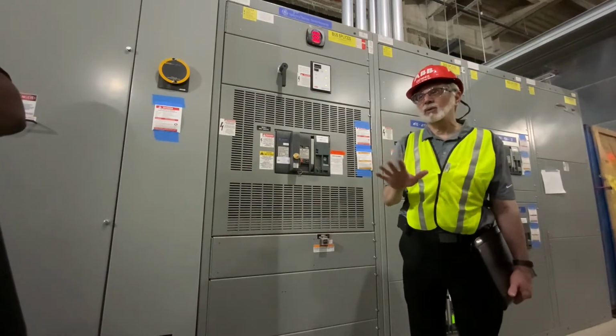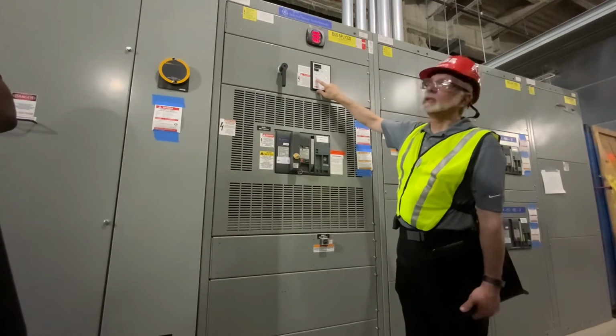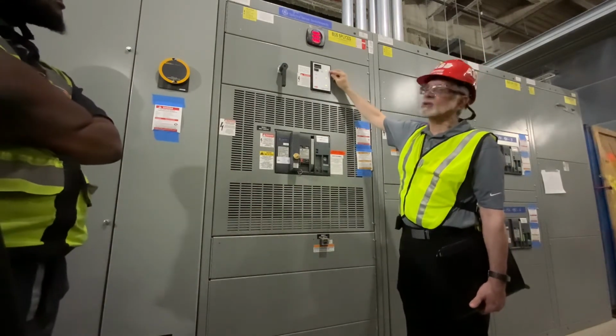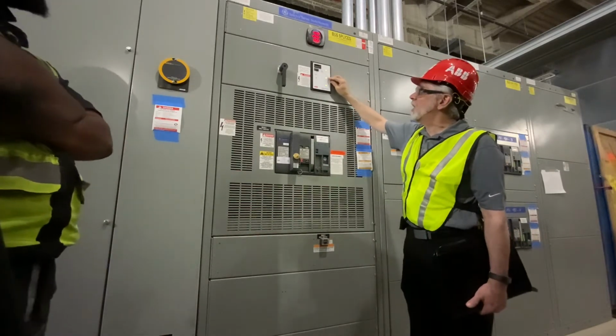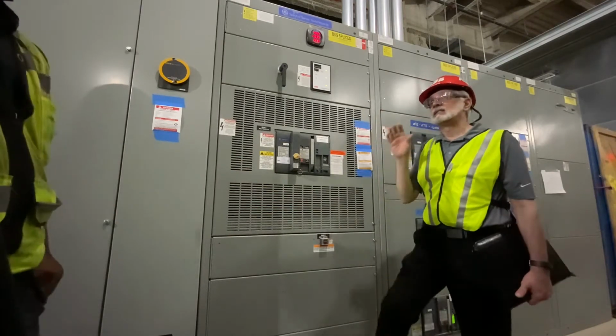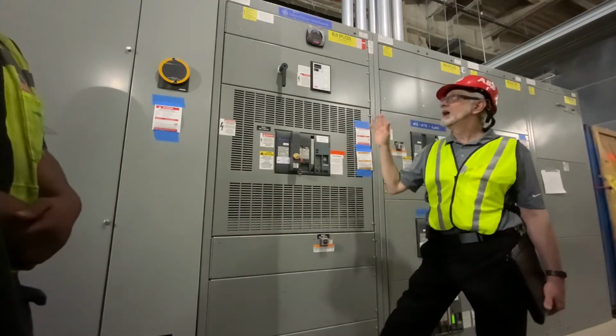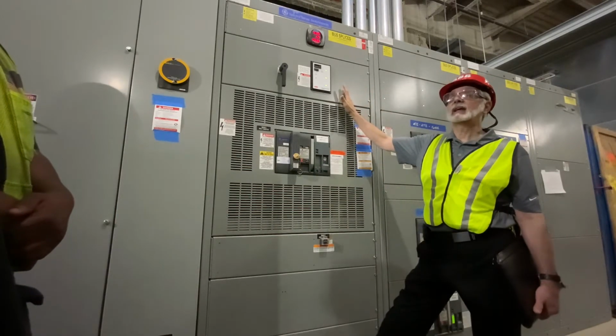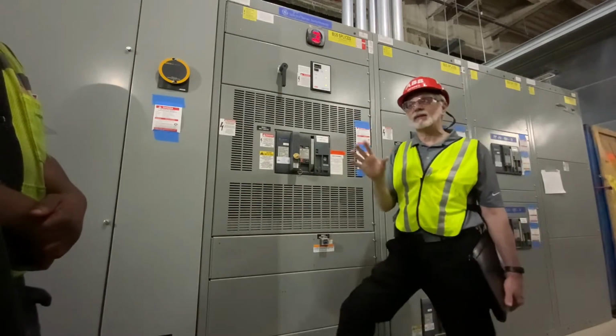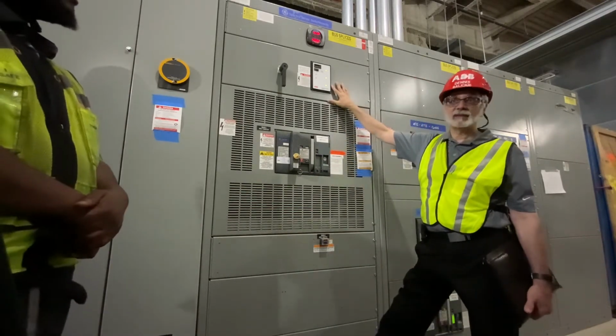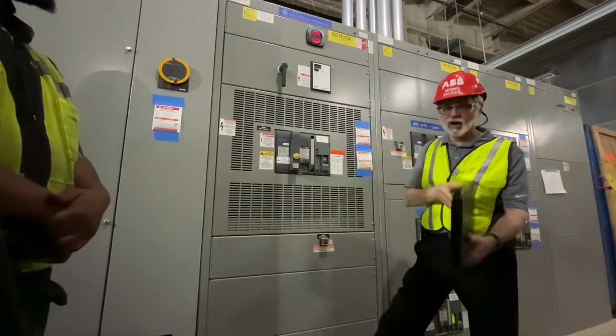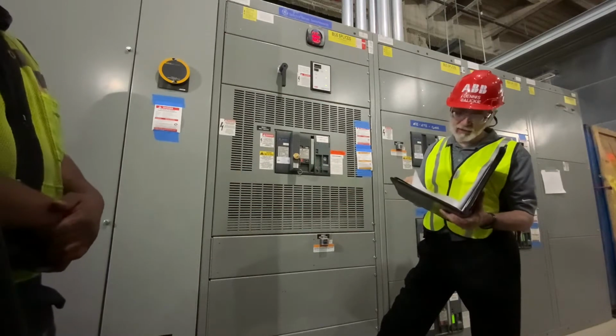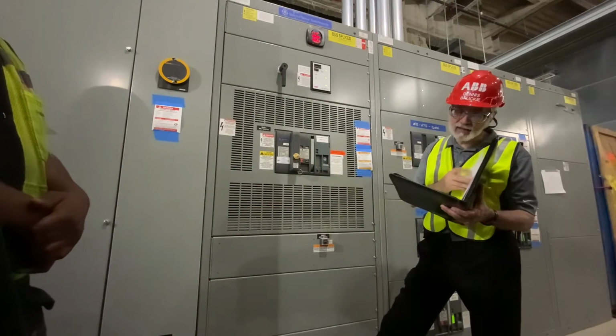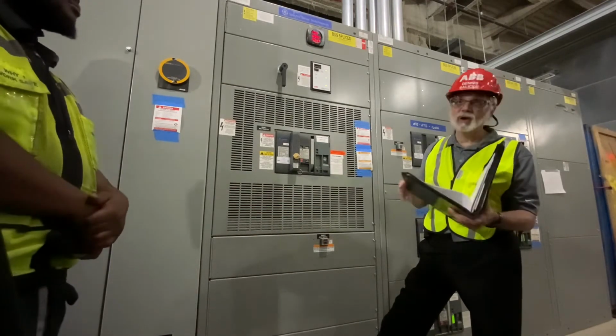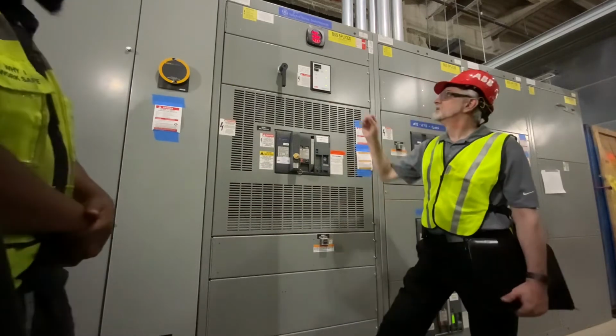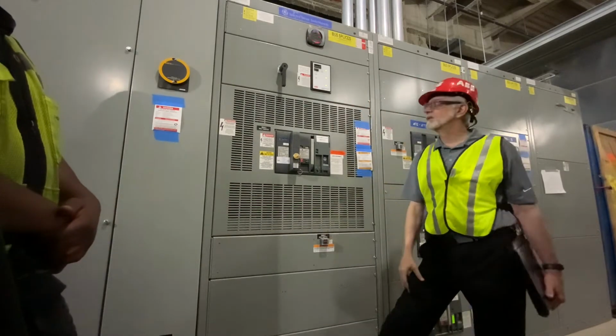From a maintenance standpoint, the one thing you want to be careful of is if this alarm is activated, or if any of these lights are not green. If you see a red indicating light, that means something of a dramatic nature has happened, and this unit has intercepted that and shunted it, but it was of such a catastrophic nature that the unit itself became damaged. Now, that would really have to be something catastrophic. The unit itself, I think, is rated like 200,000 or something like that. It's a very high rated unit, so you'd be talking something very severe for the unit to activate.